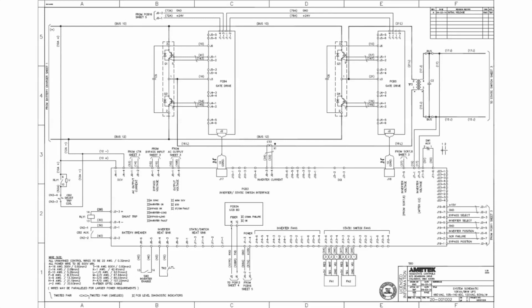So going forward, if you ever are in a situation where you are recommending a customer changes over and adds a remote manual bypass switch, then somewhere in the communication with the factory when you order it, make sure that they add a new placard for the UPS to add the instructions for the remote manual bypass switch, because you are correct, it is confusing, and it's very easy for us to make a placard. You do have to place an order for it, so the people who make the placards know that they have to make one, and the engineering team should be able to write that new procedure for you without any issues.